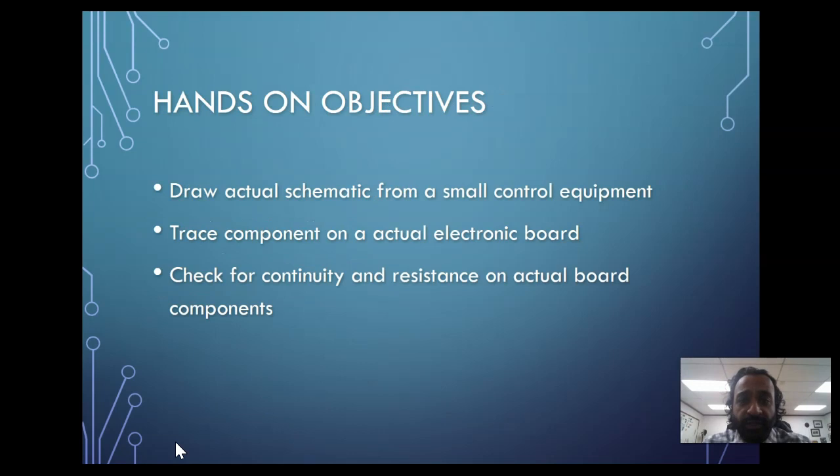For the hands-on objective, I'll give you an aquastat with all the components—very old-fashioned so you can see the components and how they function. I will trace the components, and by doing so we will trace how it works and how it's wired. Hopefully that will help you understand how schematics are drawn and what's happening on paper. It's a big transition to translate what's on paper into actual equipment. We'll also test that equipment for continuity and resistance on actual components.